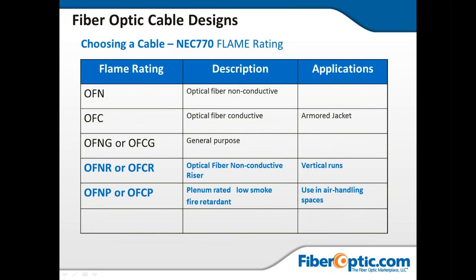These are fire codes or flame ratings printed on the outside jacket. You have OFN versus OFC — OFC means there's a metal conductor or armor jacketing in it. OFNG or OFCG is general purpose. Then you have OFNR and OFNP — riser-rated and plenum-rated — used for fire codes. Plenum-rated cable can't expel toxic smoke in areas where people breathe, such as air-handling spaces. Riser-rated is for vertical runs like elevator shafts where smoke won't accumulate.